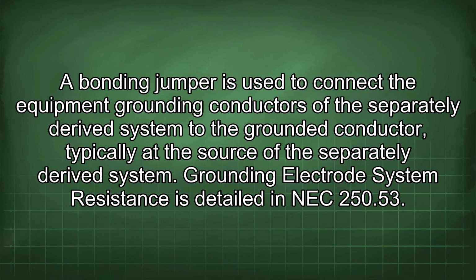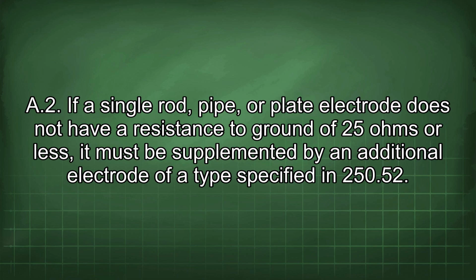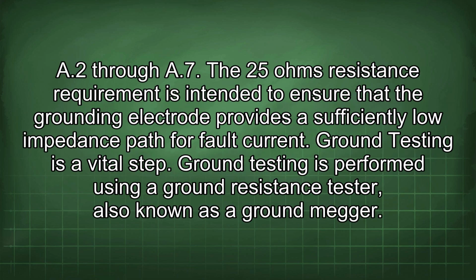Grounding electrode system resistance is detailed in NEC 250.53(A)(2). If a single rod, pipe, or plate electrode does not have a resistance to ground of 25 ohms or less, it must be supplemented by an additional electrode of a type specified in 250.52(A)(2) through (A)(7). The 25 ohms resistance requirement is intended to ensure that the grounding electrode provides a sufficiently low impedance path for fault current.